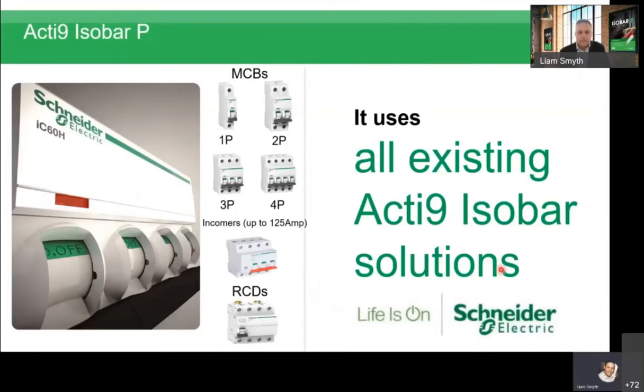It uses all our existing Acti9 Isobar solutions, so it's a very adaptable solution, with a full range of MCBs, RCDs, incomers, auxiliaries, with enhanced safety features such as VisiSafe. The green strip provides protection downstream from maintenance work. It guarantees the downstream circuit is always safe. VisiTrip signals with a red flag the defaulted MCB to reduce intervention time. It also has class 2 insulation, so double insulation to ensure continuous protection for both operators and unqualified persons.